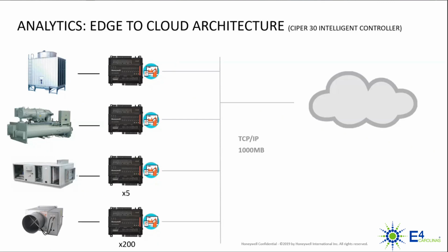This allows us to move toward predictive maintenance, getting out in front of potential failures and helping guarantee system uptime. Most importantly from an energy perspective, we can minimize slippage, the drift away from the commissioned state a building is turned over in. When a building is commissioned, that's as efficient as it will perform, and we want to keep it there as long as possible through ongoing commissioning and fault detection and diagnostics.